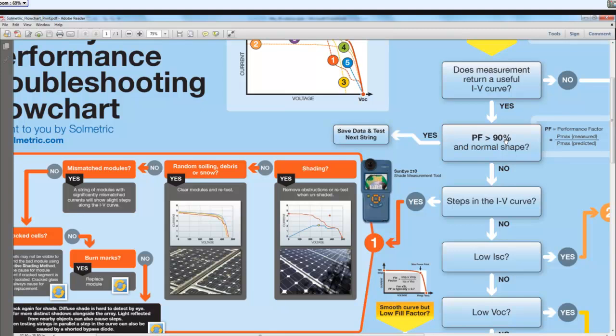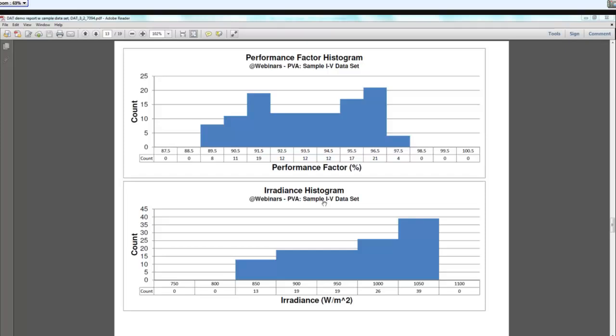You may have slightly different lighting on the modules depending on their view of the sky, or if you've got nearby shading effects that block some of the diffuse radiation. You have slight errors in your irradiance measurement, and slight errors in the voltage and current measurements. So when you add all that up, your expectation is not to be at 100, but to be in the 90s. Third-party engineering firms are very comfortable with this. If they look at your report and see that your...